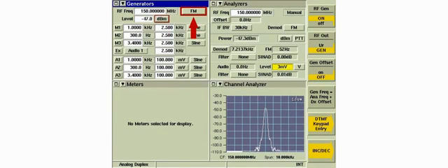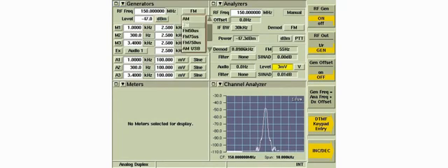The modulation button selects the type of modulation generated by the instrument. The generator can be set to produce AM, FM, upper sideband, or lower sideband. FM preemphasis is also selected here. IQ Gen is an optional feature that generates IQ modulation from stored IQ definition files.